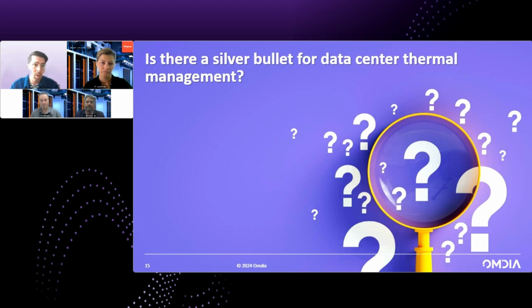So immersion cooling works, but to eliminate the power at the highest end, you need to get creative even with immersion. One thing I encourage you to think about, since I can see multiple people indicating they're going to immersion: air-assisted direct-to-chip liquid cooling is being advised by OVH, for example, a cloud service provider and user of air-assisted direct-to-chip liquid cooling, as being better. They're able to right-size the number of fans in the servers, the fans in the rear door heat exchanger, and the direct-to-chip setup to get an optimal environment.